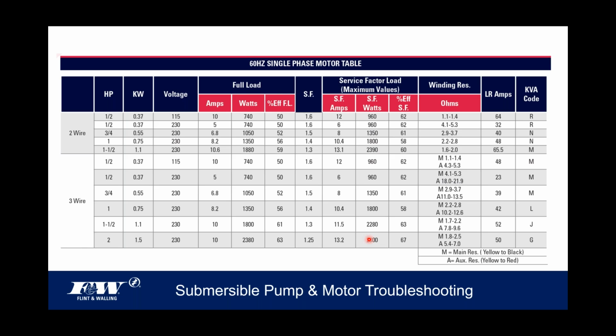So let's look at this. There's a column on the far left-hand side showing the difference between the 2-wire and your 3-wire motors. If I'm going to do a test, I need to determine, am I doing it on a 2-wire or a 3-wire? The next column over is the horsepower, so make your selection on the motor that you're going to test. If you scroll across that table, you'll come to the column called winding resistance. There are your values. They're published values.